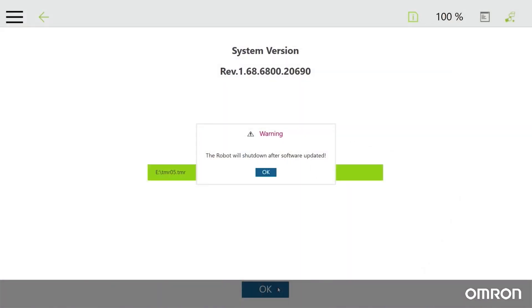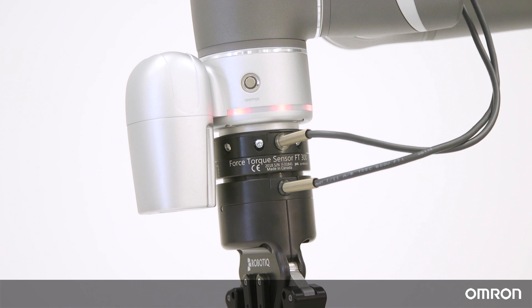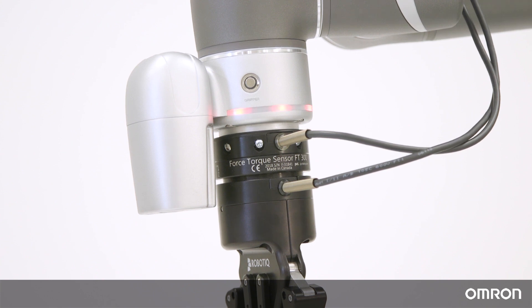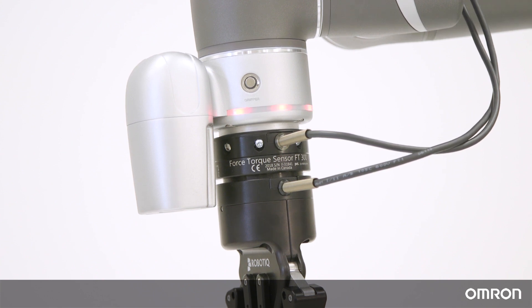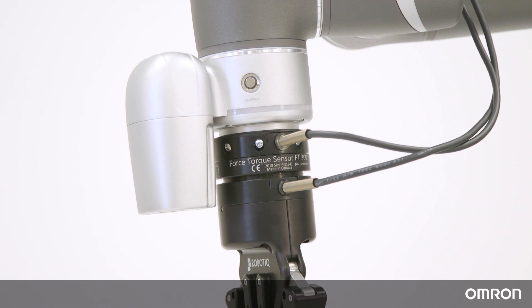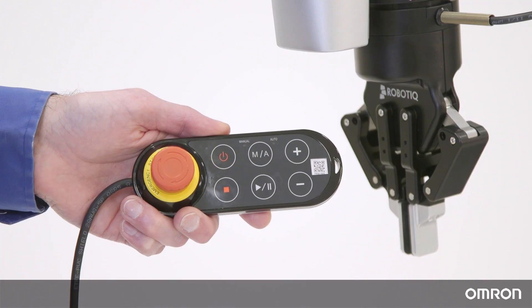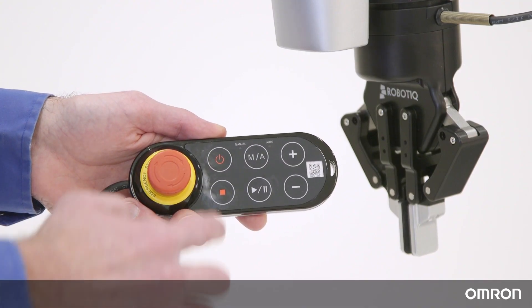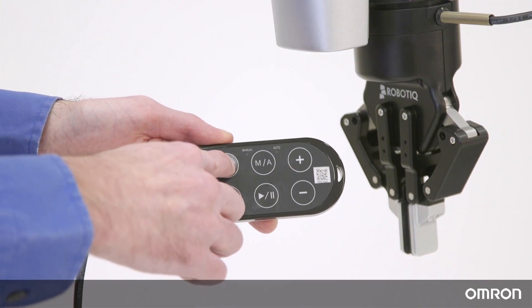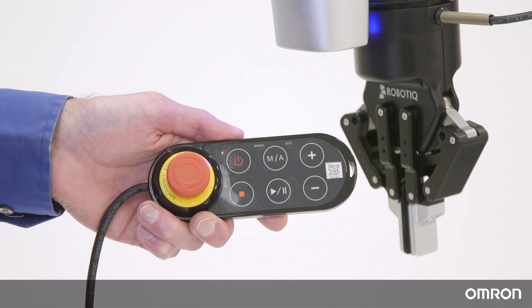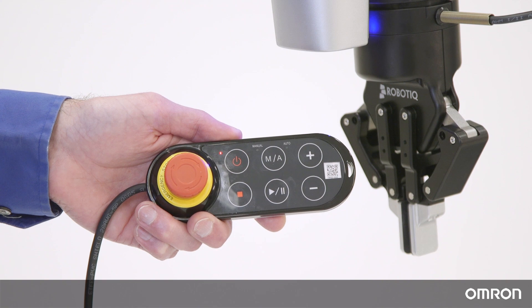When the cobot begins updating, do not touch anything. Do not unplug the USB and do not exit out of any computer windows. Keep in mind the update process can take up to 10 minutes. The update is complete when the controller completely shuts off and the blinking red light indicator on the end module also turns off. Now you may power the cobot back on by pushing the power button on the robot stick.